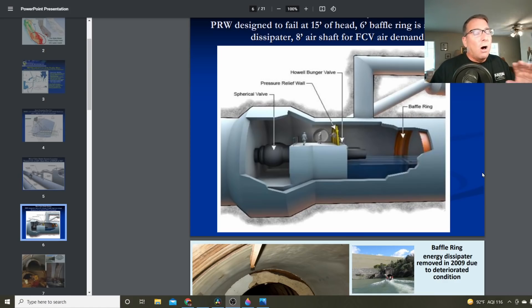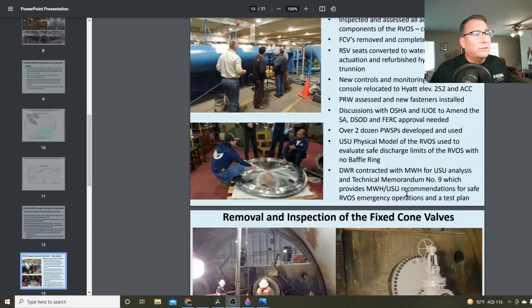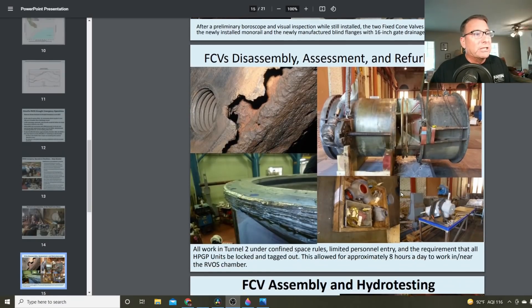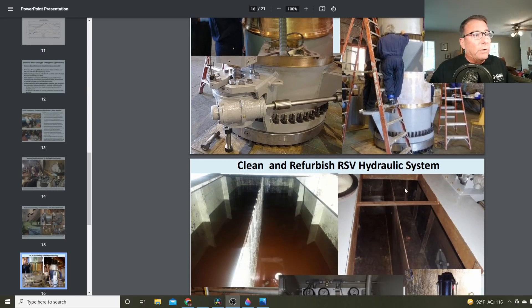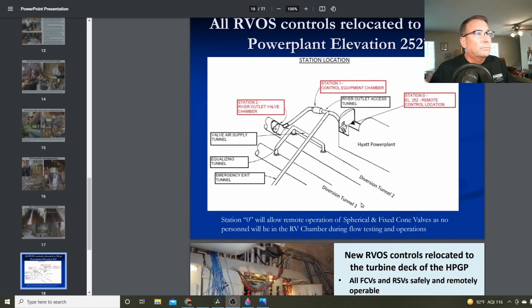It was a very dangerous situation. All of this has since been repaired and back into operation. After some teething troubles — the new valves had to be replaced, I believe, twice — they finally got an operational set of river valve outlet system valves in the RVOS system. The new ones are now hydraulically actuated remotely, so crew members do not need to be down near where the water is ejecting. They can operate it safely from a distance in a separate control facility — up in the Hyatt power plant, operating the valves remotely. Much safer setup.